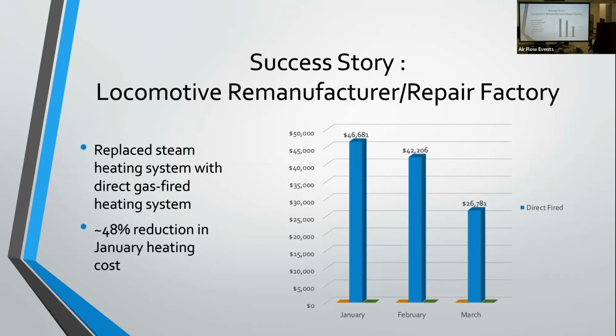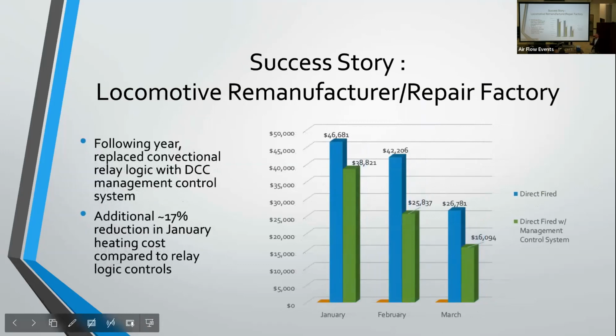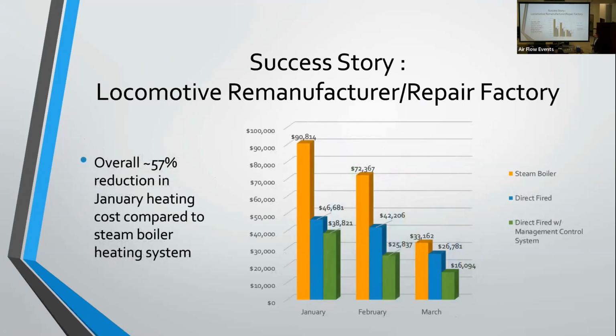So that owner was so excited that the next year they went back to the contractor and said, what else can we do to make things a little bit better? They said, well, we can replace your analog control systems with a management control system for these units. They monitored costs again for that year, and they saw an additional 17% reduction in their January heating costs just because they were using the technology to optimize the efficiency available in those units. So $46,000 down to $38,000 just by upgrading their controls. I think that was a 57% overall savings just by going to a more efficient heating system like direct fire units and then using a more sophisticated control system.